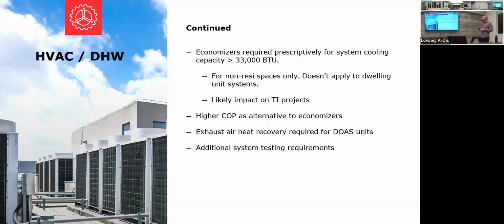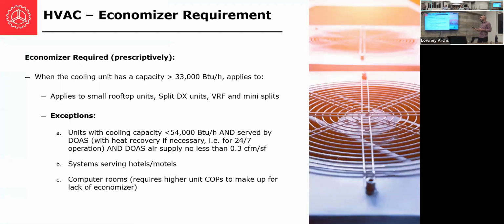And 3 tons is not a very big capacity. This space, for instance, would meet 3 tons easily. Not going to get too much into detail, but just know that this economizer requirement is more stringent in the new code, and for dedicated outdoor air systems, you might need heat recovery now. You didn't really need heat recovery modules in the Bay Area before because the climate is mild, but in some cases now you might need it, and that's just additional cost to the system, but it improves the efficiency.